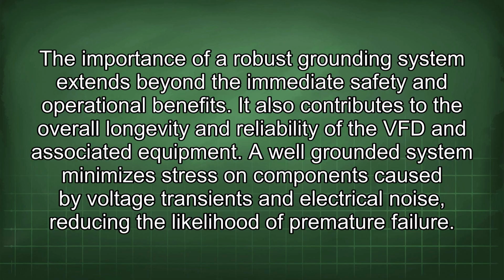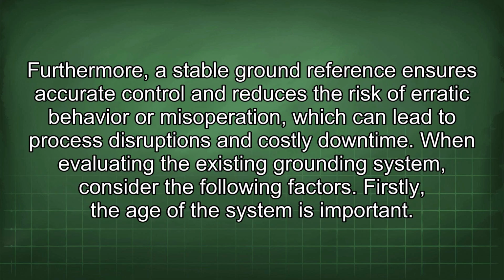The importance of a robust grounding system extends beyond the immediate safety and operational benefits. It also contributes to the overall longevity and reliability of the VFD and associated equipment. A well-grounded system minimizes stress on components caused by voltage transients and electrical noise, reducing the likelihood of premature failure. Furthermore, a stable ground reference ensures accurate control and reduces the risk of erratic behavior or misoperation, which can lead to process disruptions and costly downtime.